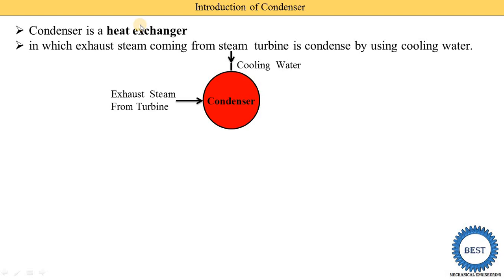In these condensers there are two possibilities: the exhaust steam from the turbine and the cooling water are mixed — this is called direct contact type heat exchanger — or there is indirect contact type. In indirect type, a pipe is used; cooling water is supplied through the pipe and steam passes from outside. When heat exchange takes place, steam is converted into water called condensate, and the temperature of cooling water increases and is further supplied to the cooling tower.